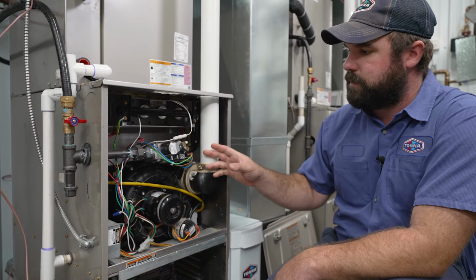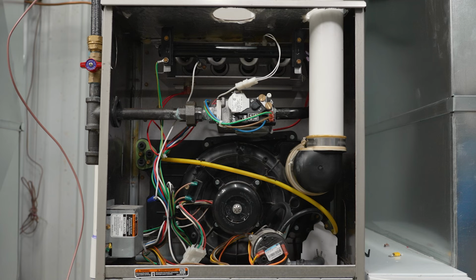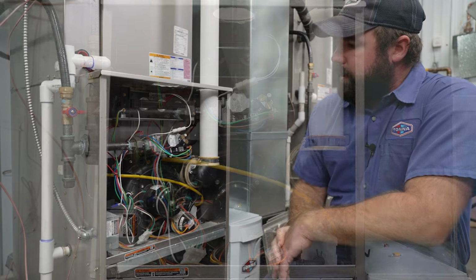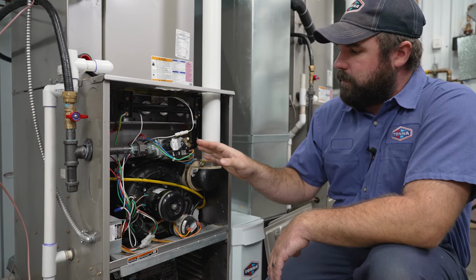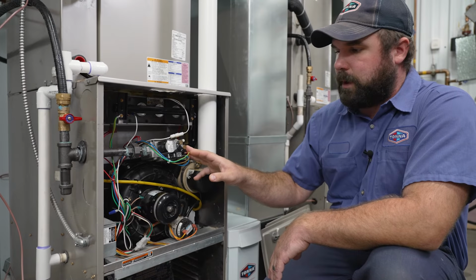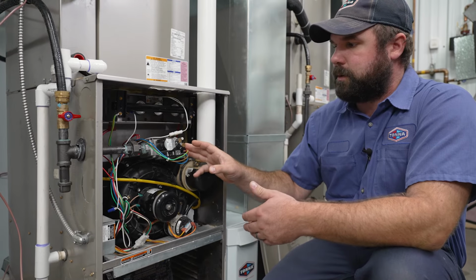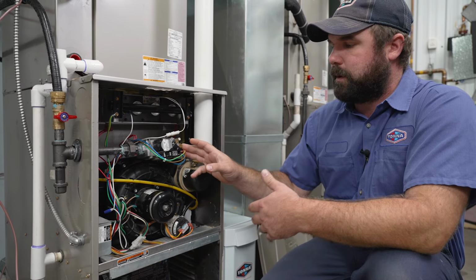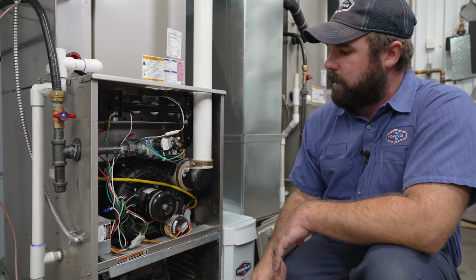We check the gas pressures on that, the incoming pressure and the outgoing pressure. The incoming pressure is controlled by a regulator. And then we check your outgoing pressure to make sure that's set up correctly as well, all to make sure the equipment is running as properly and efficiently as possible.